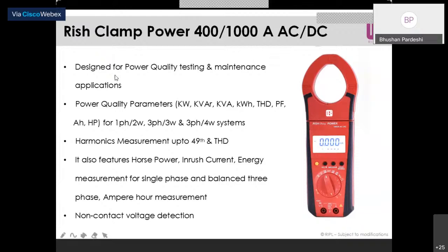Now, as I said, it's used for power quality testing. Power quality itself indicates that it can measure harmonics. So one can measure harmonics up to the 49th and THD in this single meter. This is a handheld device which can measure 49 harmonics of your voltage and current.